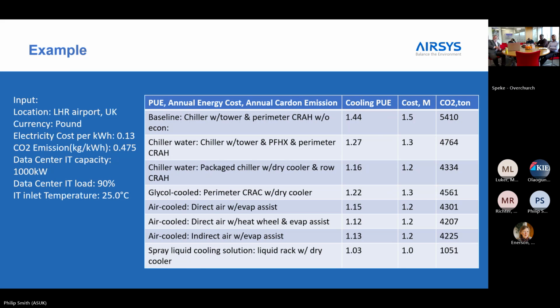When you look at the overall efficiencies of all the established means of cooling IT, liquid cooling 1.03, all the way up to traditional old-time legacy equipment, which can be up to 1.5. So half the energy used in the facility is for your cooling. With liquid cooling, it could be 3%. And if you start to recover the heat from the dielectric and use it for low-grade heating within your building, you can get a PUE less than 1, so to say. So 0.95, 0.97, something like that.